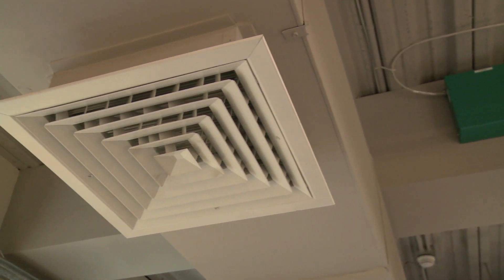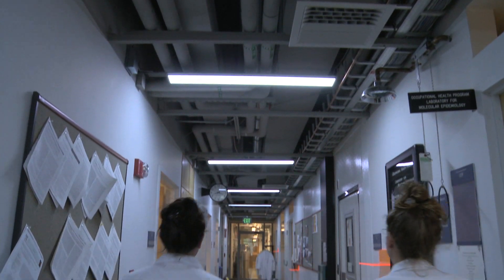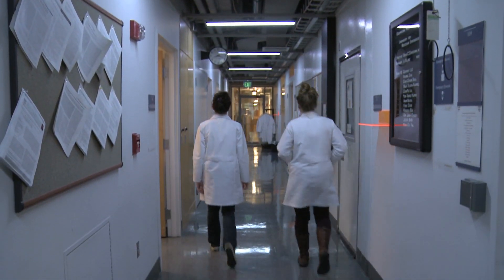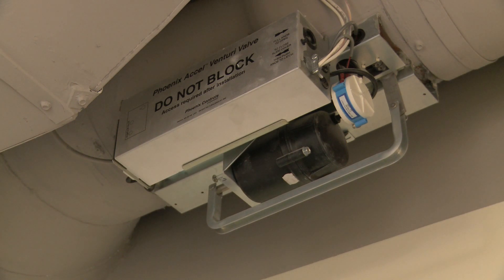With the Aircuity system we're able to drive that down much lower. During occupied times here we're at four air changes per hour minimum, and then during unoccupied times we drive it down to as low as two, which is in our plan for future modification to the system.